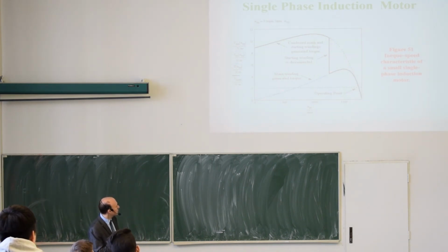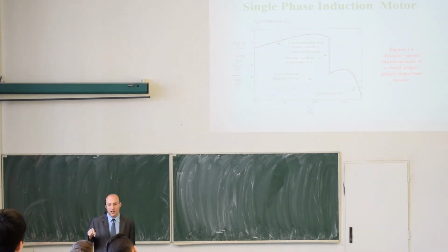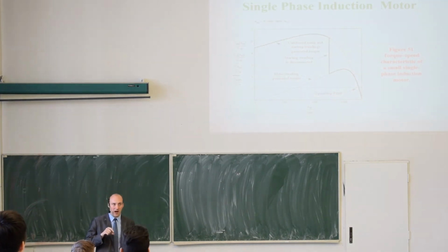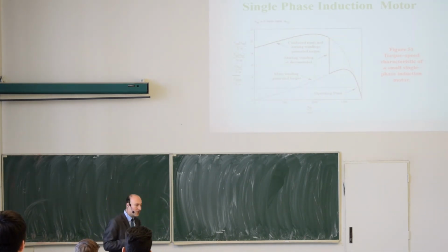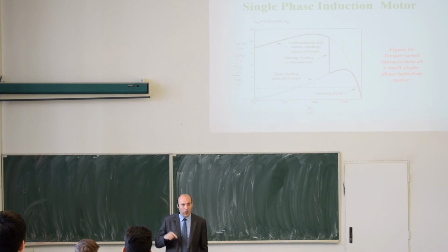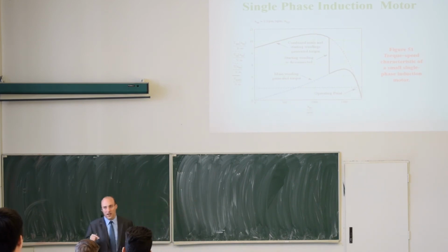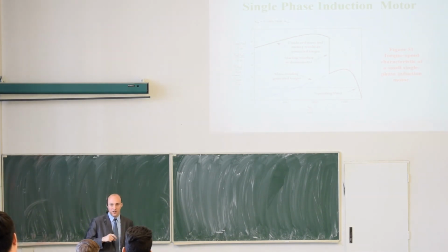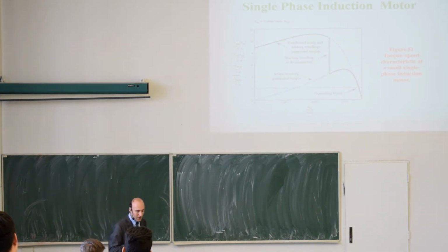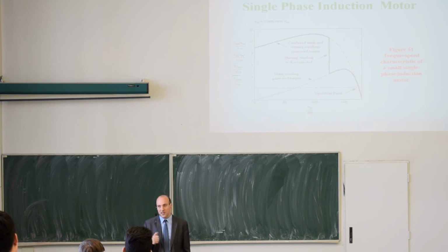So those induction motors can also be directly three-phase motors. If you buy a three-phase induction motor and connect it to a single phase with an external capacitor, it may run in this mode as a single-phase induction motor. But it's not very convenient to use it because you're basically wasting the third winding that you have in the stator. It's better to have a ready-made single-phase induction motor, which is only two windings and an external capacitor.